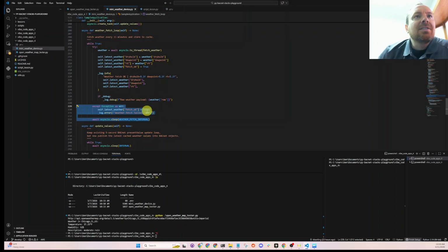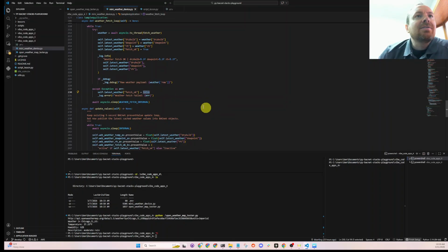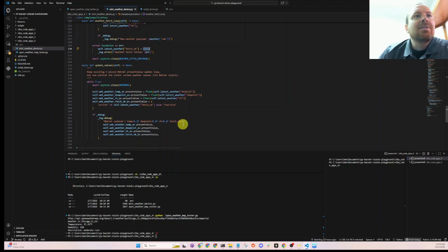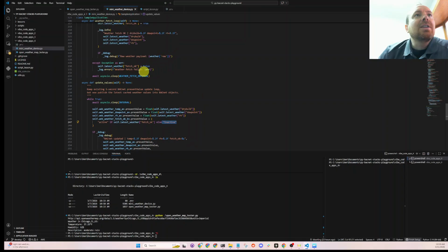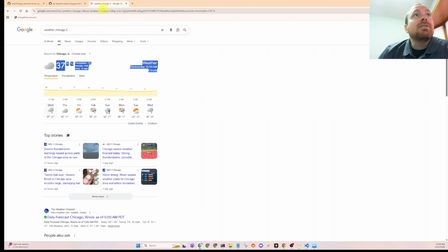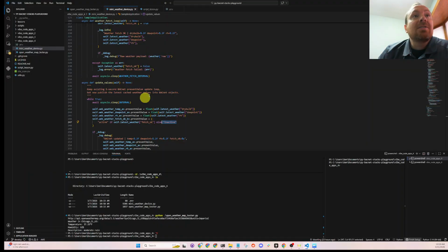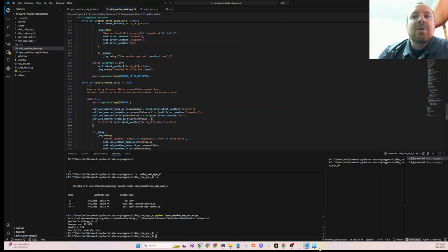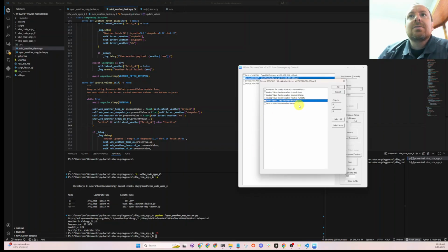You see something here that I think is supposed to be active or inactive. Maybe BACpypes handles this behind the scenes, but we could simulate this later. Oh no, it is actually in here. So if web weather fails in our GET request, which is just like we did through the browser, if that fails, like the internet goes down or OpenWeatherMap goes down, this BACnet point will go false.